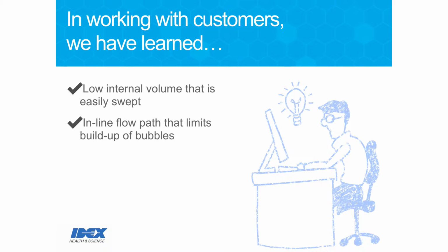Also, a fully swept path was another request from many of our customers. They said, we can't really have a dead end in our system. What a dead end will do is trap a bubble, and that may cause problems with dispense accuracy. It also creates some carryover issues. So if you are flowing two reagents through a fluidic path with a dead end, the reagents may end up mixing and can cause some pretty bad effects in some cases.